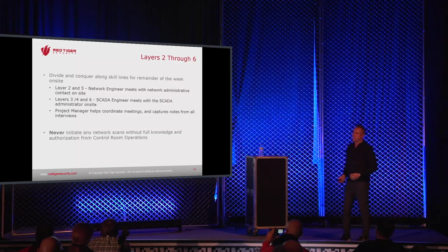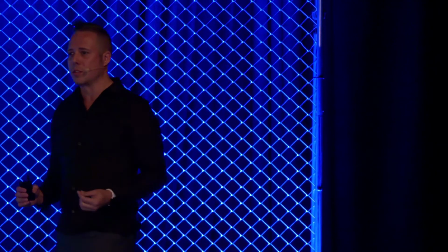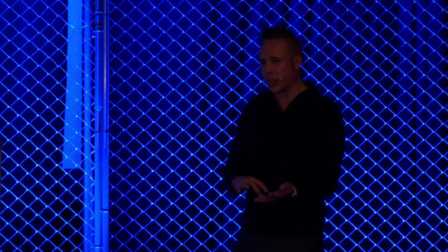Usually the physical security process is not the main goal of the assessment, but you want to make sure that if they're governed by NERC CIP or, let's say, CFATS, those physical requirements are there at the facility. The main part of the physical security review is to make sure that the assets used to manage the plant are being physically protected properly, so that the switches and cabinets are locked, access to the control room resources is locked, and physical security and cybersecurity are interwoven properly.